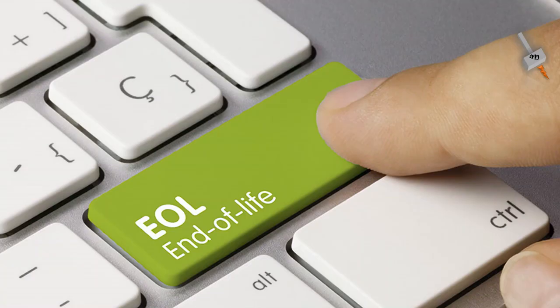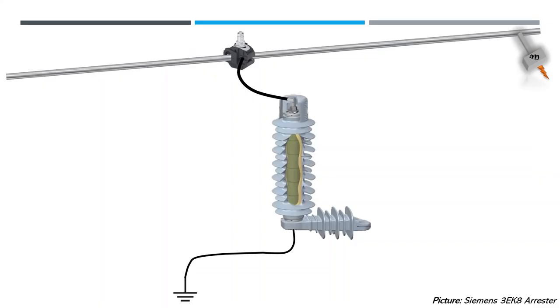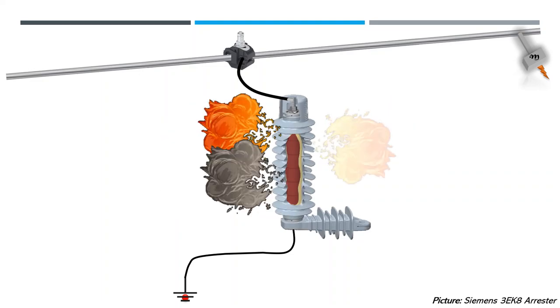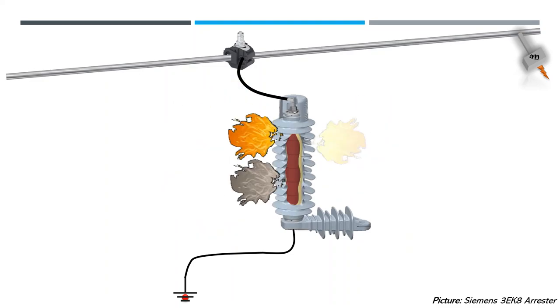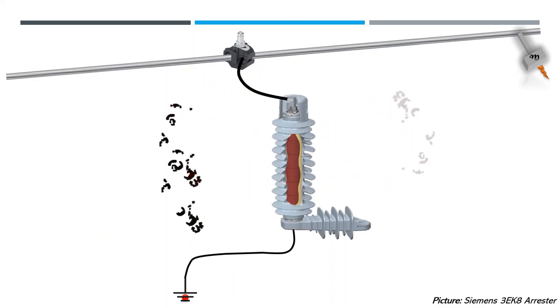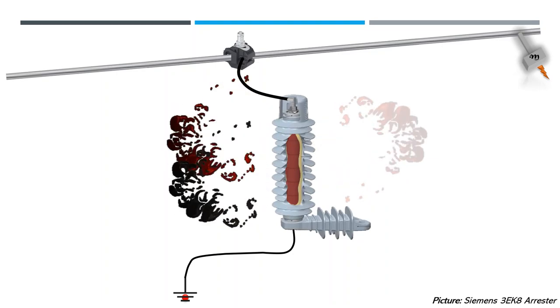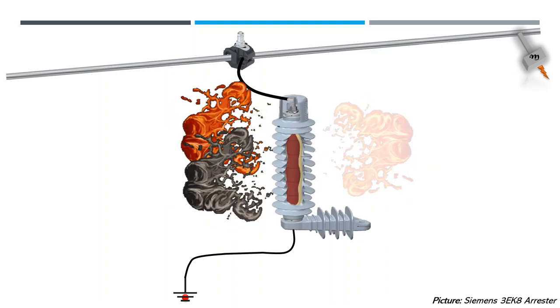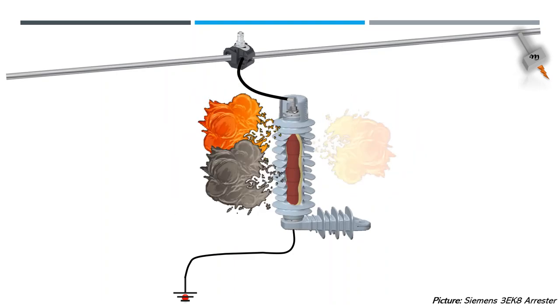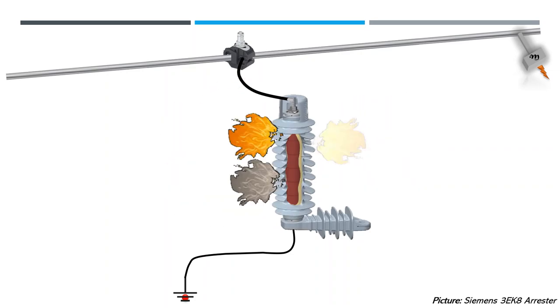Every equipment manufactured by man has an end of its life. When an electrical surge which has energy level beyond the lightning arrester capability is diverted to ground, it results in a pressure relief event and at the same time creates a dead short circuit. Thus, the end of life event of a lightning arrester results in tripping of a grid circuit due to breaker operation.